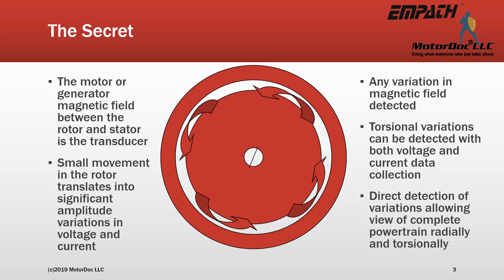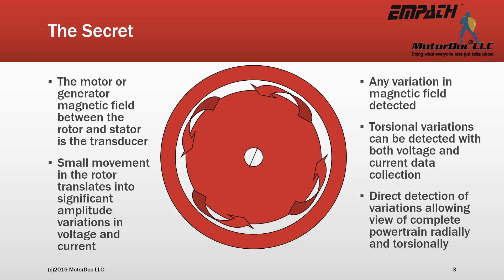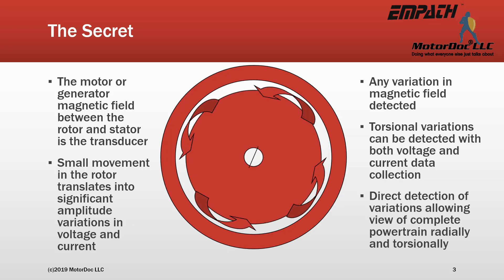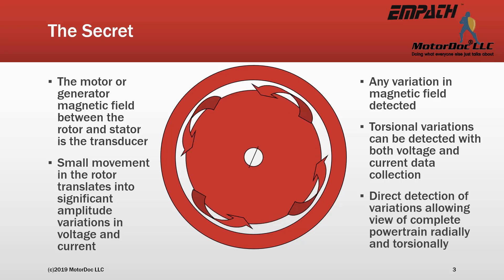When looking around the line frequency, it is common to demodulate or remove the carrier frequency in order to look at low-frequency issues in motor current. However, you must use modulated data to determine the actual severity. The purpose of electrical signature analysis is to identify any variation in the magnetic field. The detection is related to both side-to-side movement and torsional movement and is related to the turning and twisting of the rotor. The same thing works for generators but is performed as voltage signature analysis.